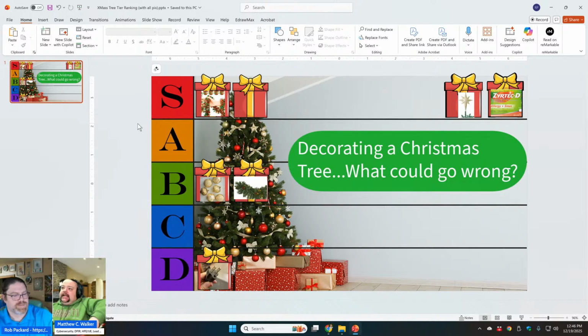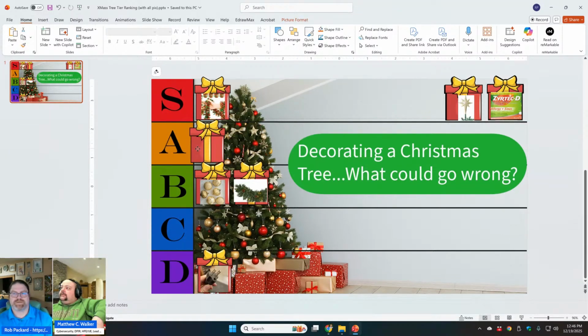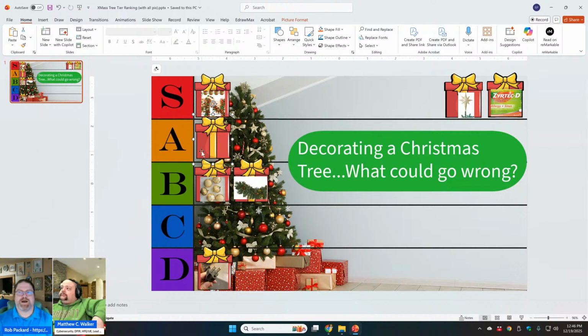How does the FDA approach this? Because when I was a firefighter, I was also an EMT, and we came across standing height injuries that would have hit the critical task level. What does the FDA require when looking at something like a tripping hazard like this? Because most people will fall and not sustain a critical injury, but the potential for that does exist. Yeah. I think they would probably bump it up from no harm to this kind of harm, but I don't see them going much beyond that.